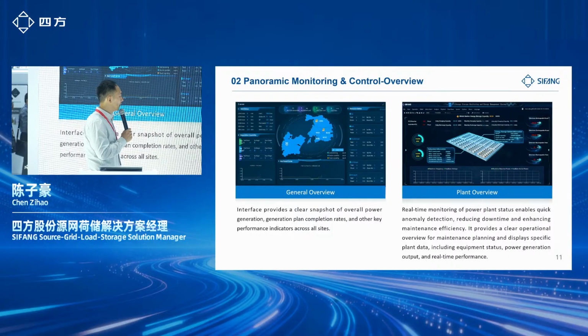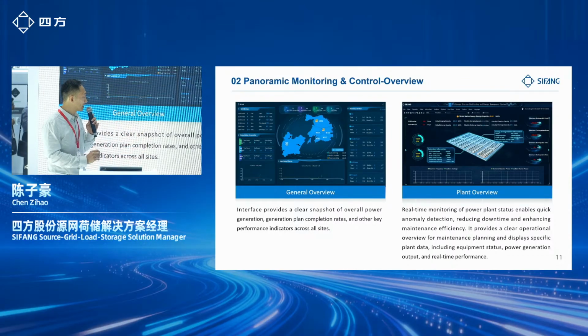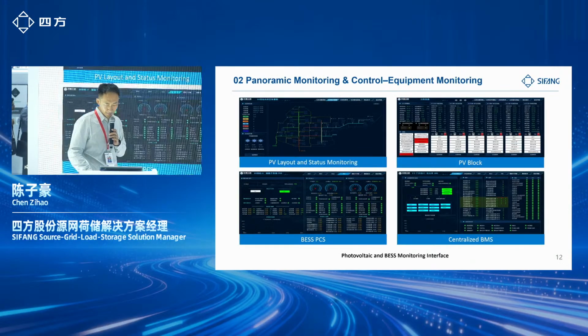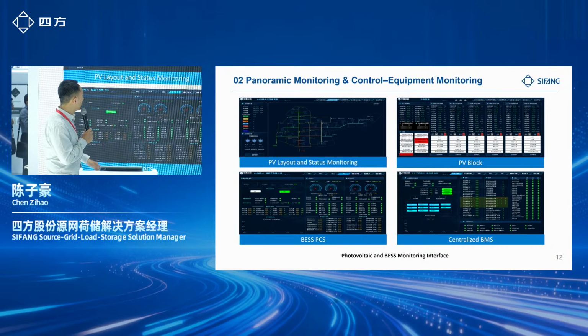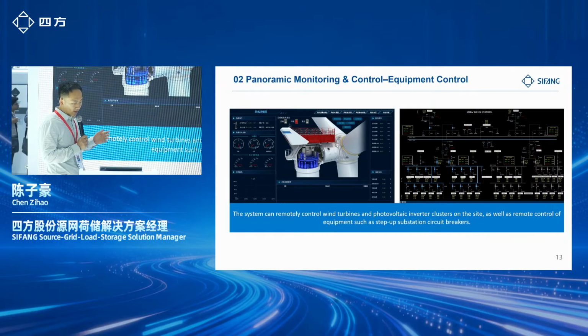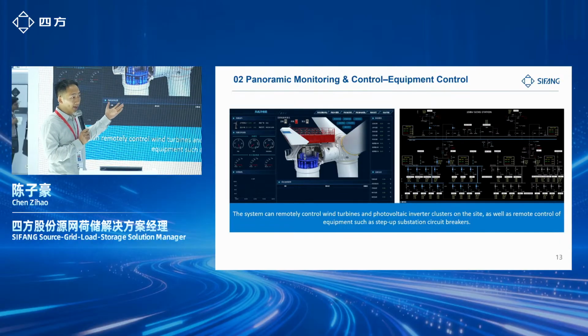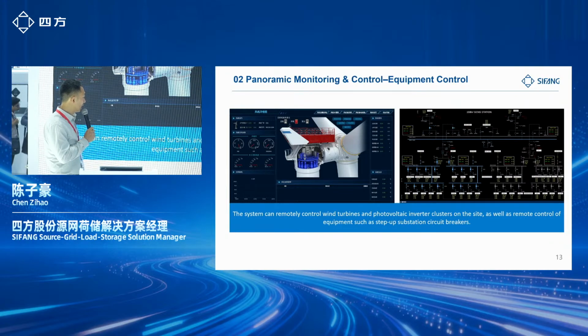And also the plant level, we provide this quick abnormal situation detection to reduce the downtime and enhance the whole efficiency of the maintenance. For the equipment level, we have this PV layout, status monitoring, PV block, and also the BESS PCS, BMS level monitoring. Except the monitoring, we also provide the remote control function. Like for all the primary equipments, like the wind turbines, solar inverters, also the BESS PCS, we all support the remote control.